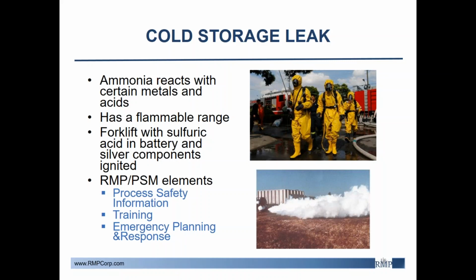Regarding RMP PSM, the process safety information prevention element is particularly important to ensure all dangers associated with chemicals and process elements used in the system are properly documented and hazards are addressed. If more accurate safety information had been obtainable by the responders, the tragedy could have been avoided. Employees and responders should be fully trained on the dangers of the chemicals they are working on and know how to respond to them in an emergency. Important lessons to take away from this accident are to never enter a visible cloud of ammonia, measure the concentration when responding, and carefully control any potential ignition sources at your facility.